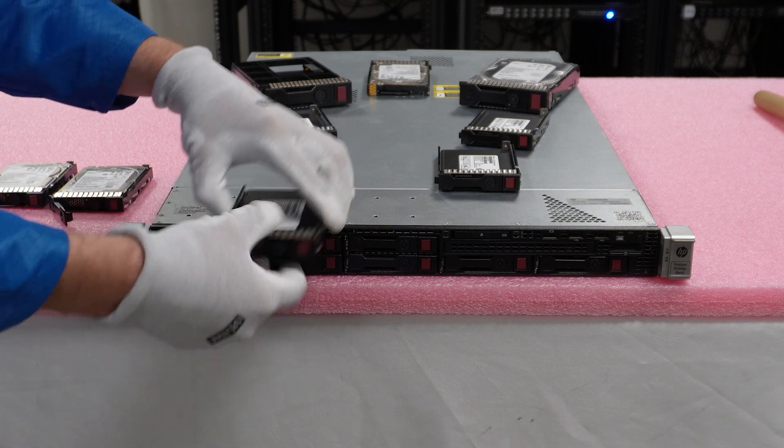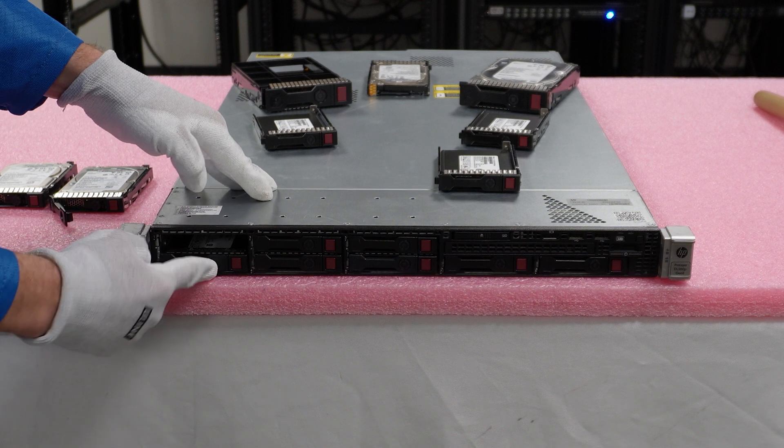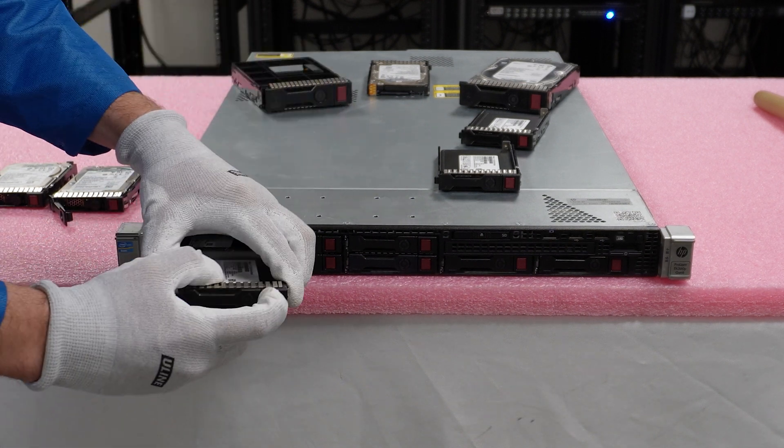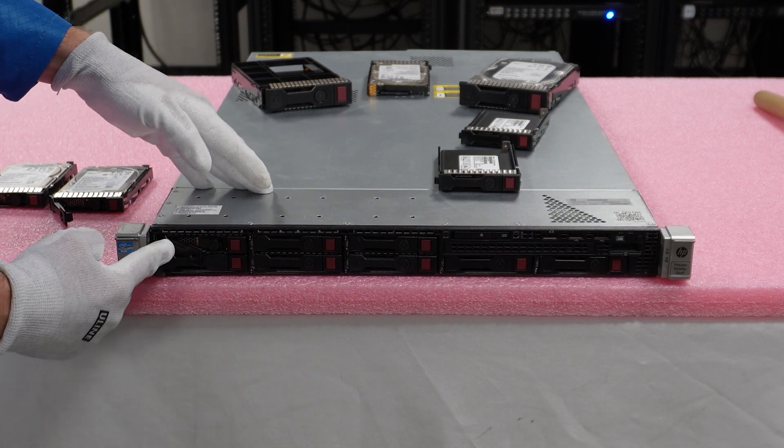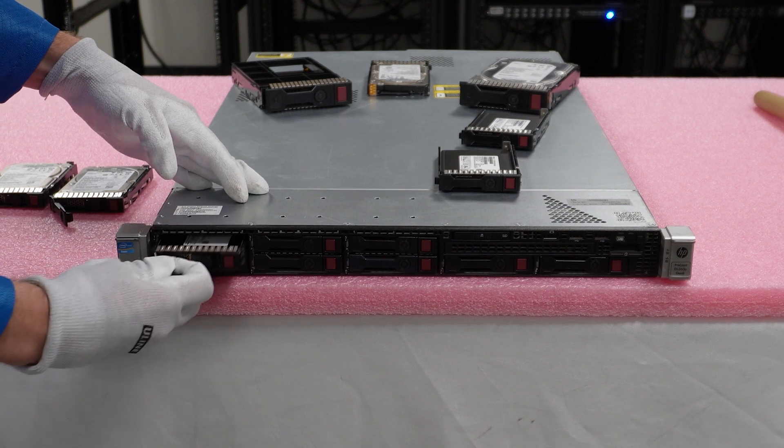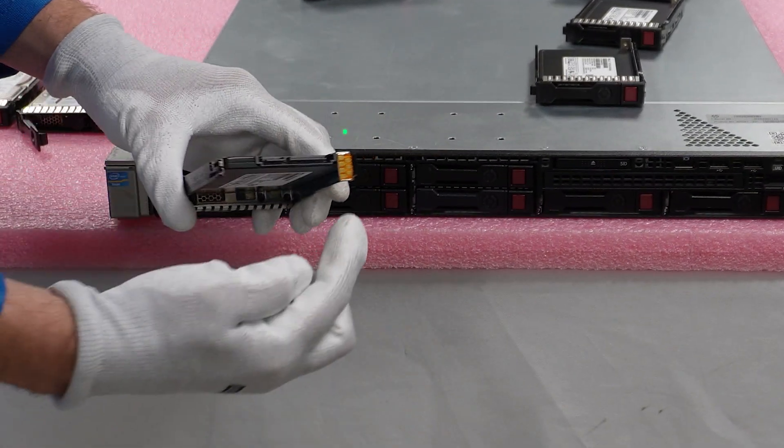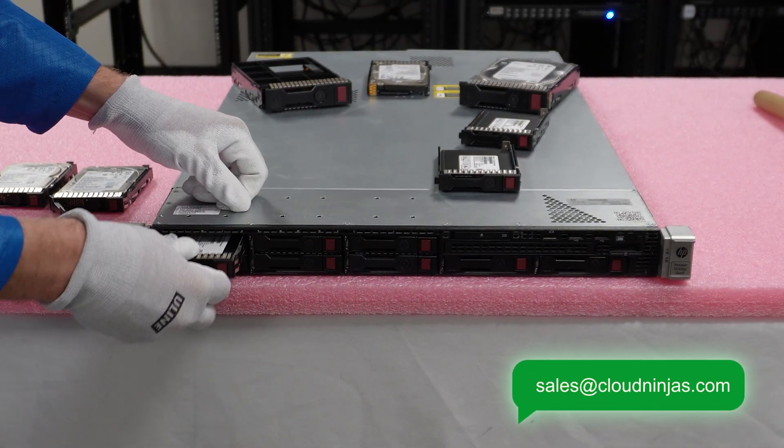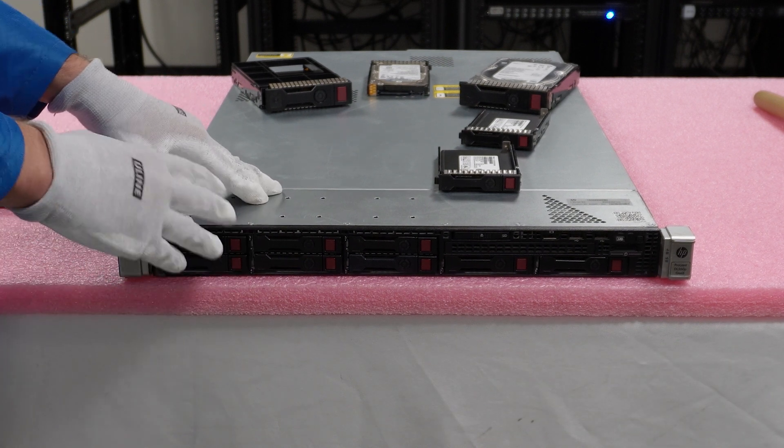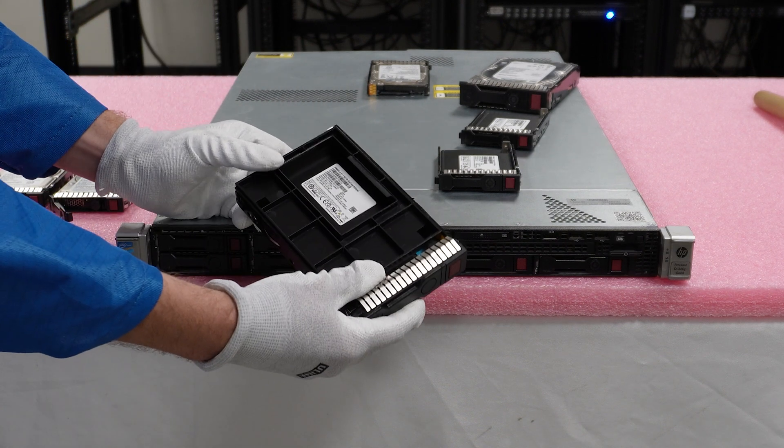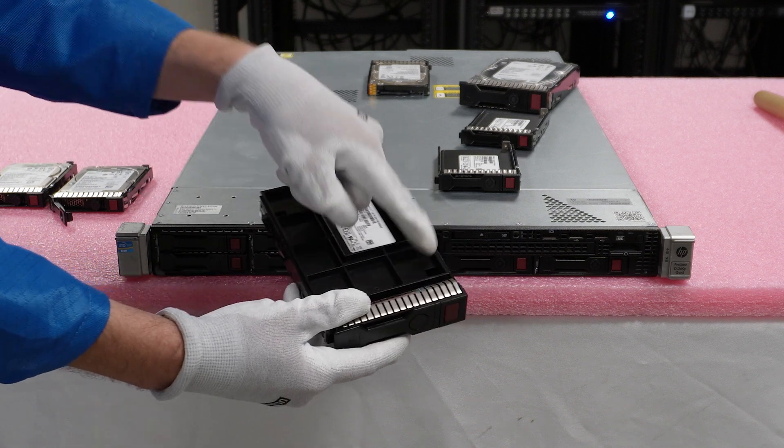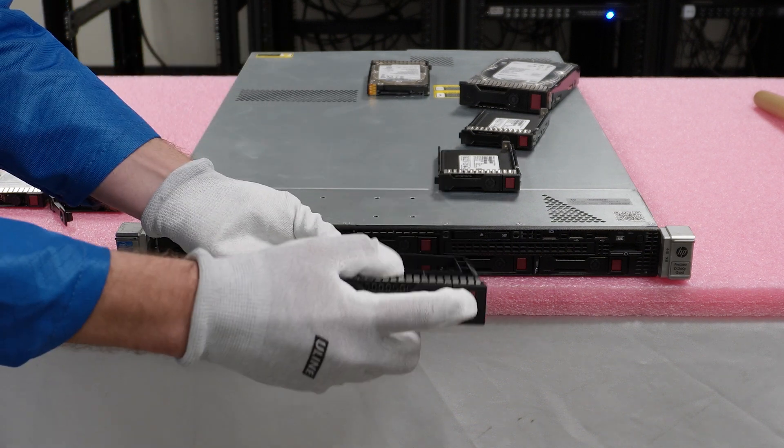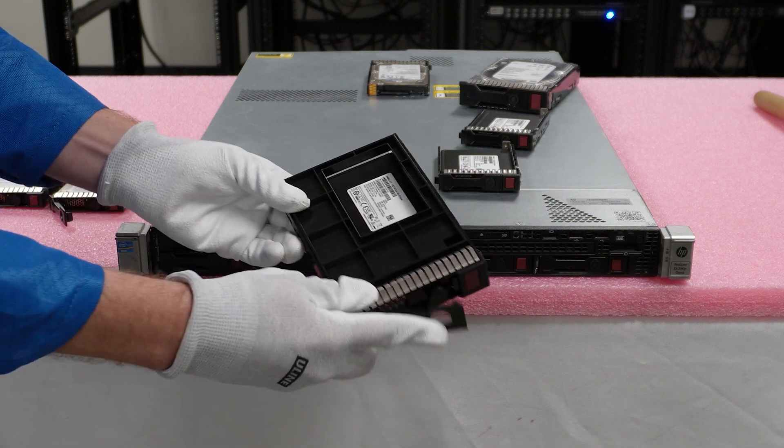which are going to be faster and more reliable. One of the things we always say is a good upgrade to extend the life of an older machine like the Gen 8. Just open your tray and slide it in. When you get right here, it'll hook on and you just push it and clip it close. It's very easy. I did want to note that with our trays, you are getting the connector, so the appropriate setup. If you go to our website to order solid state drive upgrades, you will get the right tray with the correct setup for your Gen 8. If yours is a large form factor, because solid state drives are 2.5 inch, we will have the kit with the converter or adapter with the 3.5 inch tray to make this work for your specific chassis.